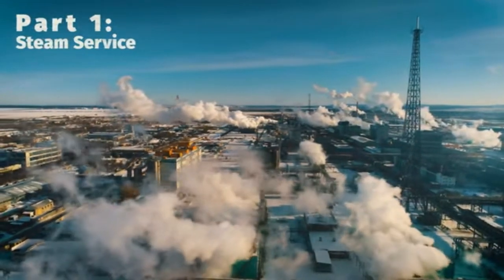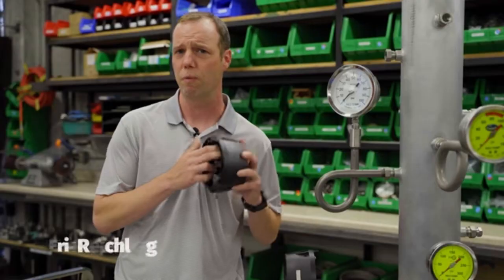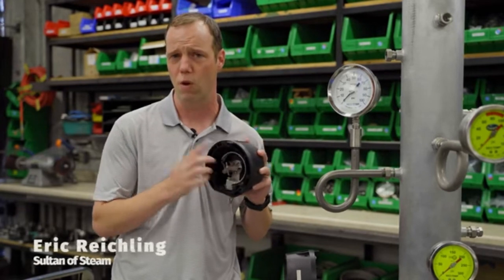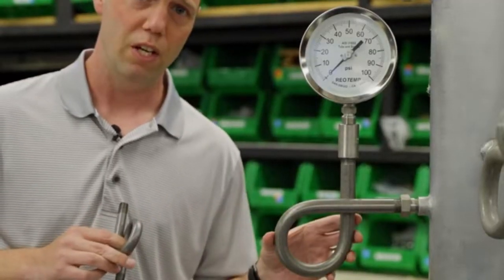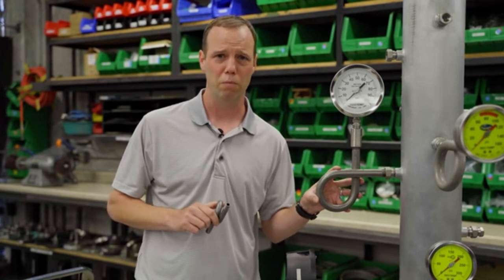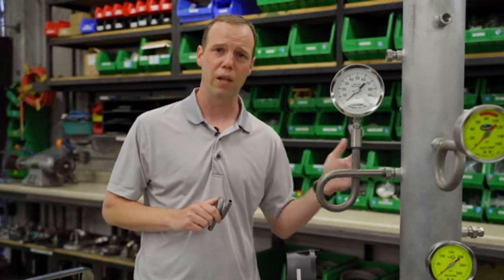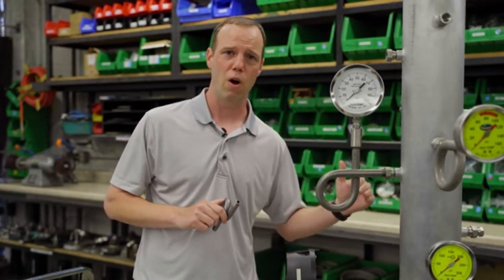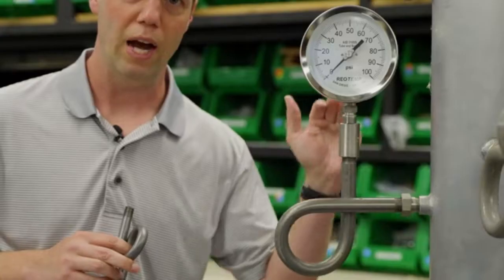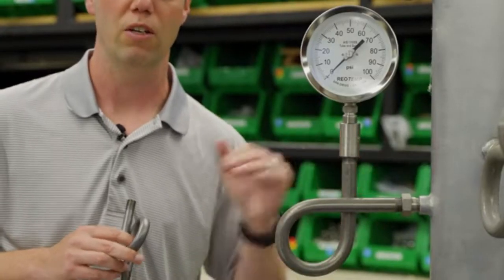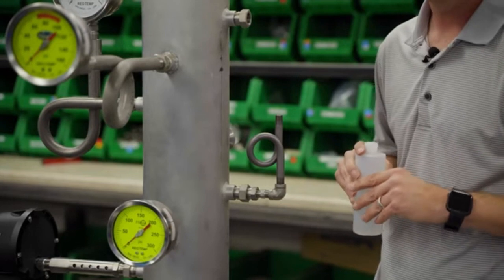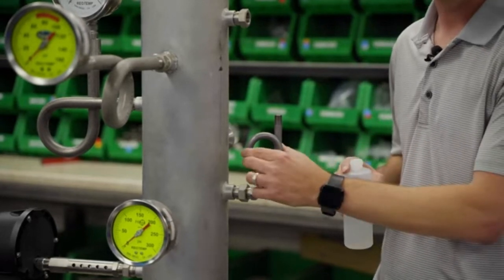In steam service, the goal is to prevent steam from entering the Bourdon tube of the pressure gauge or the sensing element of a pressure transducer by creating a water barrier. Using a pigtail siphon, steam condenses into a trap at the bottom of the loop. And as pressure is applied, the steam pushes that water into the gauge, isolating it from direct contact with the steam. When installed, pigtail siphons should be filled with water prior to use.